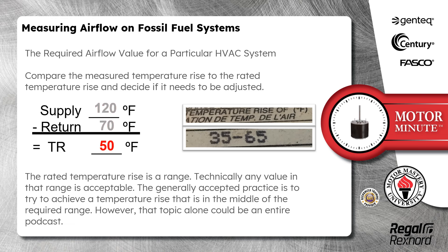Compare the measured temperature rise to the rated temperature rise and decide if it needs to be adjusted. The rated temperature rise is a range; technically, any value in that range is acceptable. The generally accepted practice is to achieve a temperature rise that is in the middle of the required range. However, that topic alone could be an entire podcast.